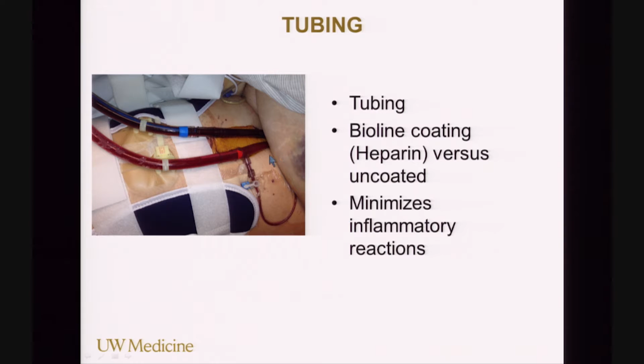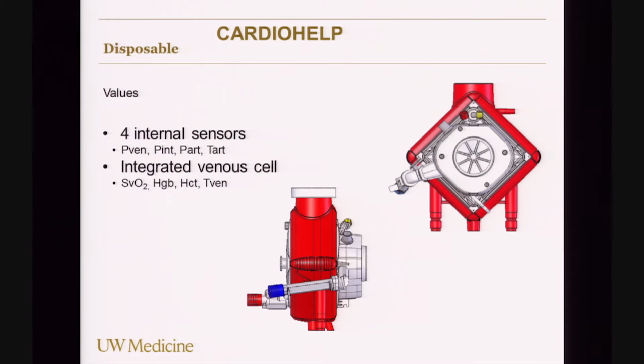Just another picture of the tubing setup, in red coming in, blue going out. There are internal sensors built into the device which give us a lot of information in the software package. It tells us the pressures that we're seeing both on the venous side, internally to the machine, and on the arterial side. It gives us a continuous temperature reading, and it also gives us continuous readings on SvO2, hemoglobin, and hematocrit through a sensor as well. So it's really nice continuous data that you get.